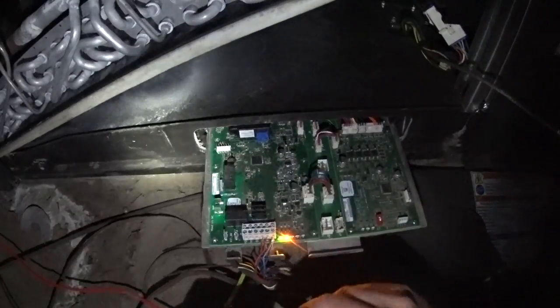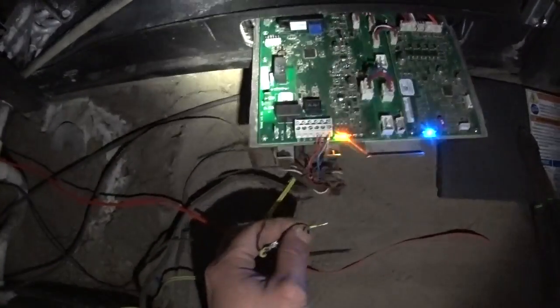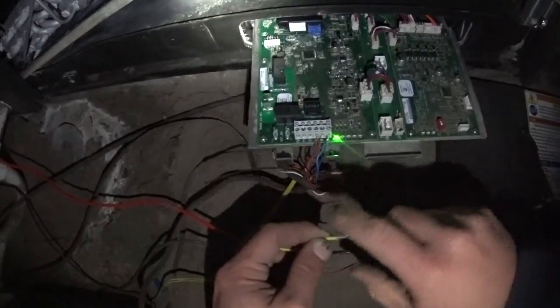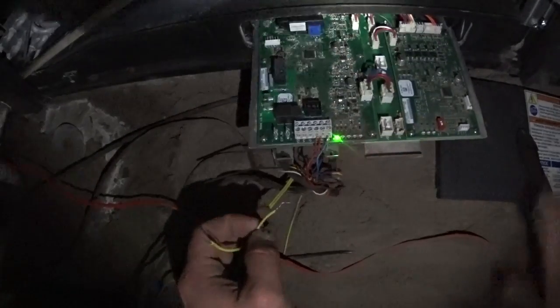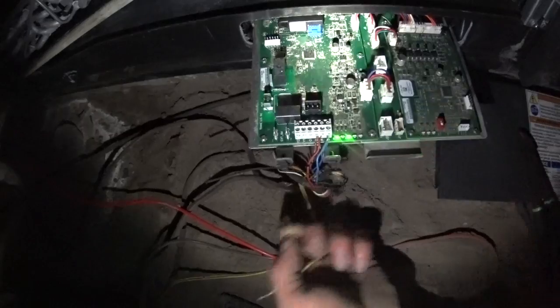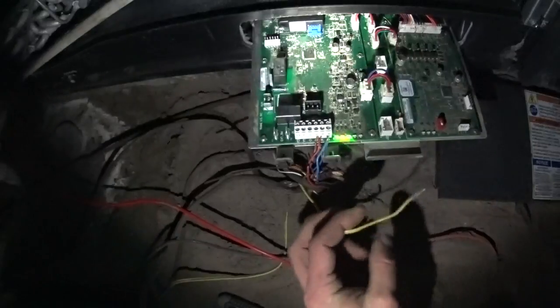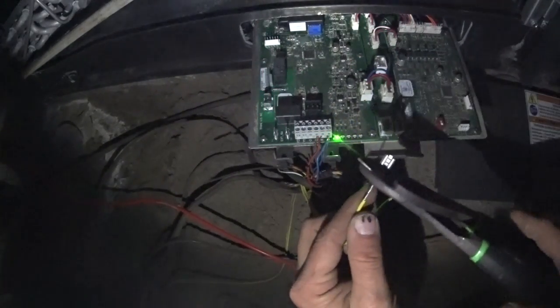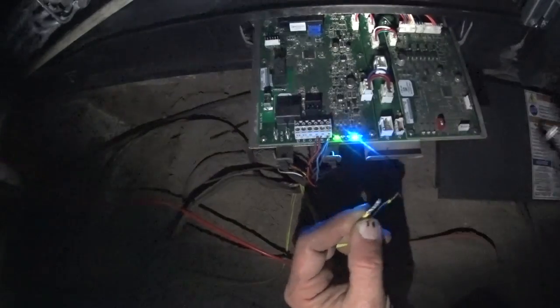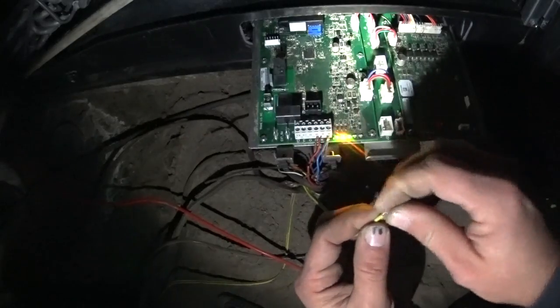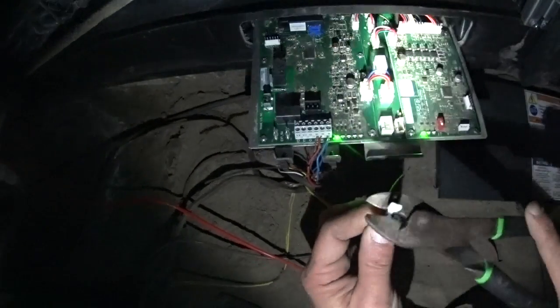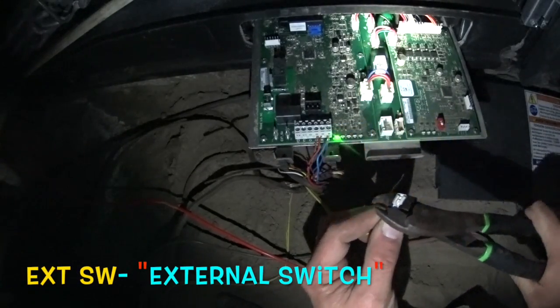So, on this particular series of Hyperion air handler, the float switch does not go into the low voltage wiring. If it goes into the low voltage wiring, it will throw a code that doesn't make any sense, and you'll be chasing your tail trying to figure out what's going on. So they provide you with these two terminals labeled EXTSW, and as you might be able to decipher, those terminals are for an external switch.